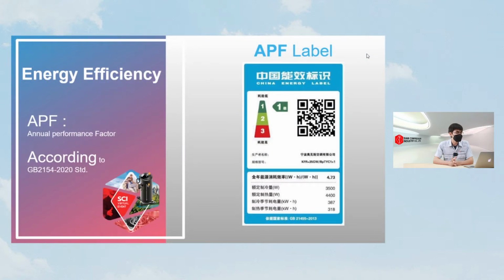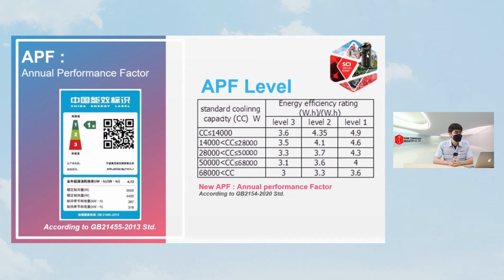Like any other air conditioner, APF is an energy efficiency standard. APF is the standard for the VRF heat pump in the air-cooled type. APF is short for annual performance factor, and it was generated by collecting data from working hours of office and rental shop buildings in Beijing, China. APF was separated into three levels for different cooling capacities, as shown in the table. For example, for cooling capacity lower than 14,000 watts, it is 3.6 for level 3, 4.35 for level 2, and 4.9 for level 1. And of course, level 1 is the best here.